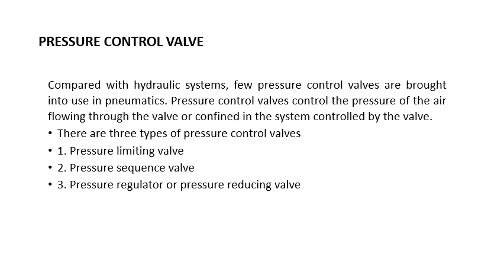Compared with the hydraulic system, few control valves are brought to use in pneumatic systems as well. Pressure control valves control the pressure of the air flowing through the valve or confined in the system controlled by the valve. There are three types of pressure control valves: pressure limiting valve, pressure sequence valve, and pressure regulator or pressure reducing valve. The working principle is the same as the hydraulic system — only the working medium changes. Pneumatic systems use compressed air or other gases.